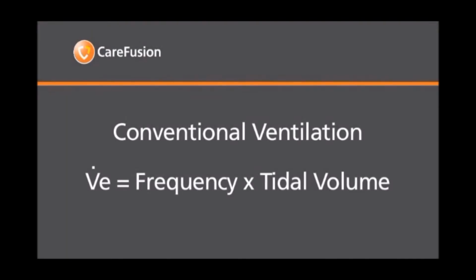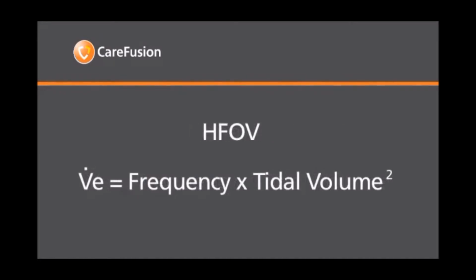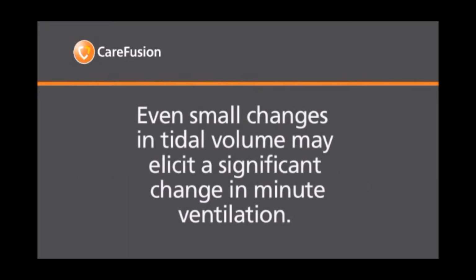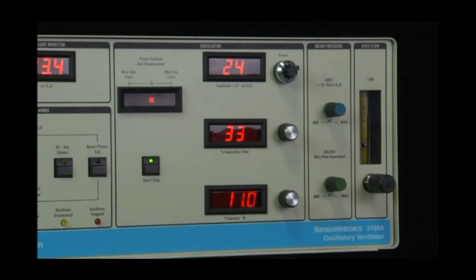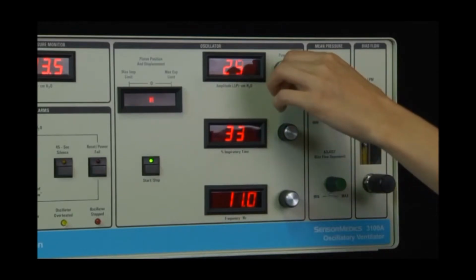Unlike conventional ventilation, in which minute ventilation is expressed as frequency multiplied by tidal volume, minute ventilation for HFOV is expressed as frequency times tidal volume squared. It's important to understand this relationship since it demonstrates that even small changes in tidal volume may elicit a significant change in minute ventilation. As discussed in the previous section, altering the voltage to the linear motor by manipulating the power control directly affects the amplitude.